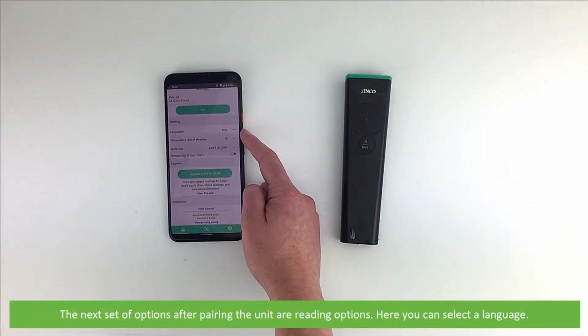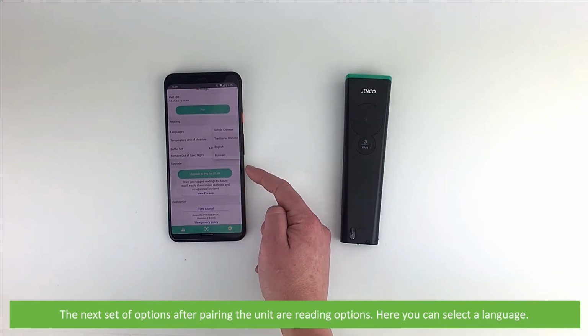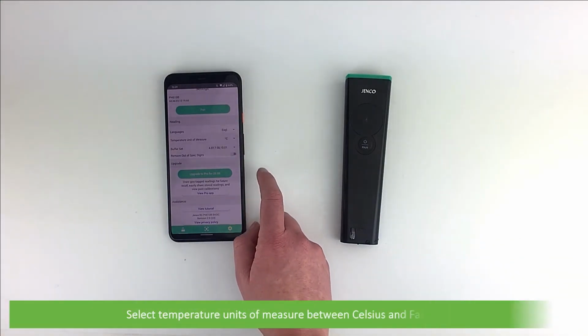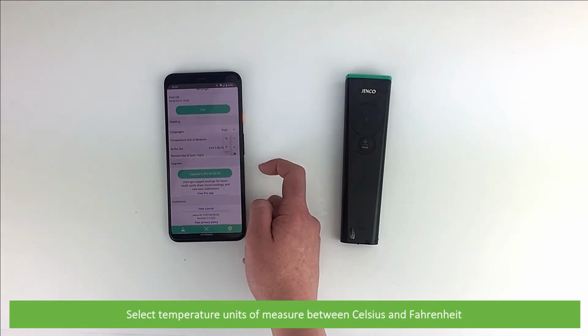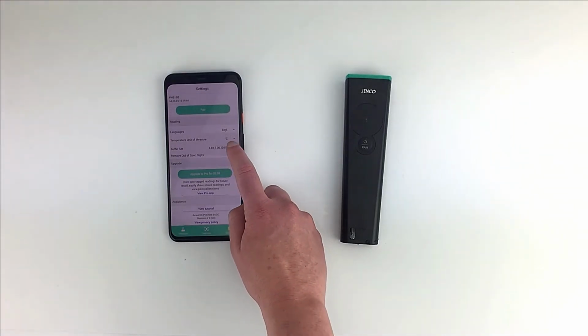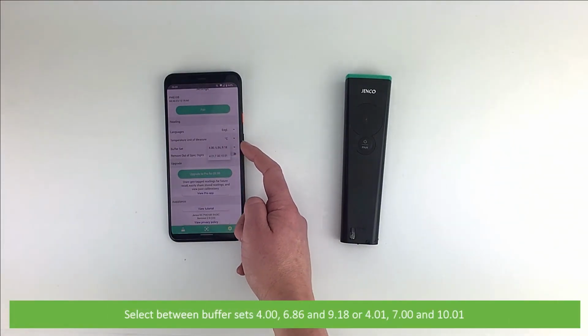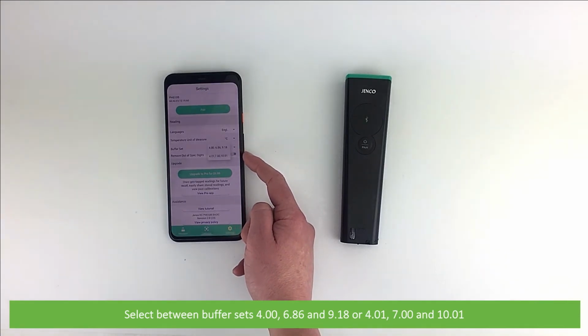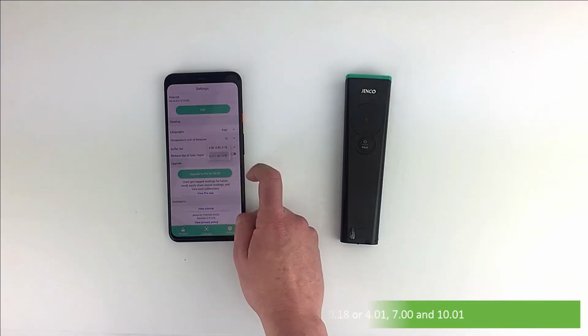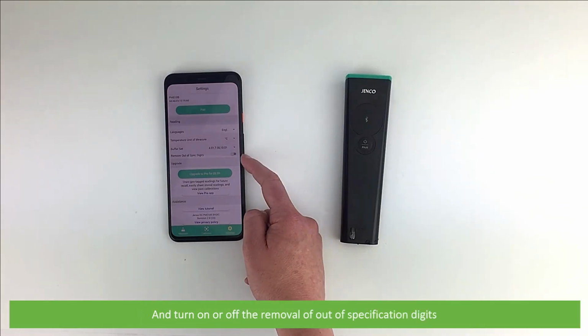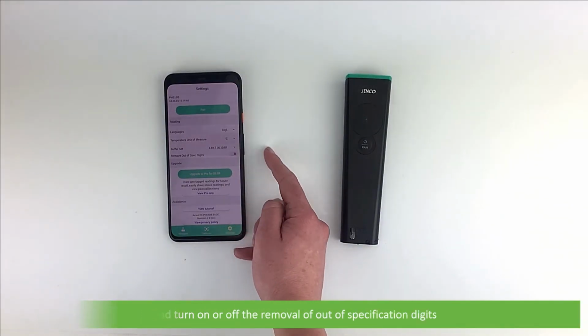The next set of options after pairing the unit are reading options. Here, you can select a language, select temperature units of measure between Celsius and Fahrenheit, select between buffer sets 4, 6.86 and 9.18 or 4.01, 7 and 10.01, and turn on or off the removal of out of specification digits.